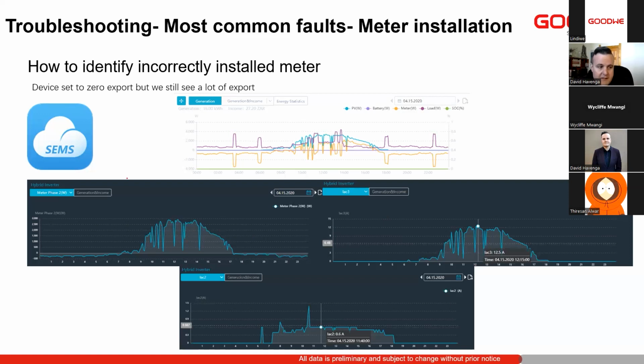So clearly the customer swapped phase 2 and 3 on the inverter, but they did not swap phase 2 and 3 on the smart meter. So with the unbalanced output, as we know, it was reading load on phase 3, but it's outputting it on phase 2. So very important, if we fix the phase rotation, to fix it on the smart meter.